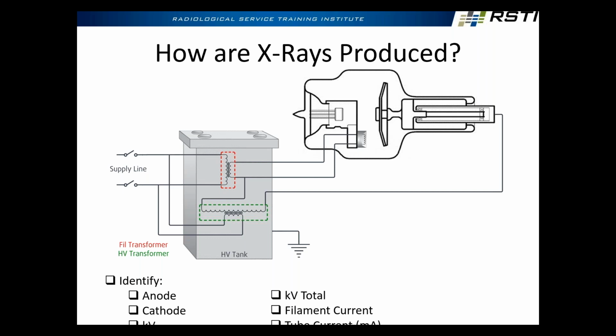On the left-hand side, we have the cathode. On the right-hand side, we have the anode or target. The cathode usually contains a pair of filaments, a small filament and a large filament, that provide us with a small and large focal spot. Those do a couple of things for us. Generally speaking, resolution is controlled by focal spot size. The smaller the focal spot, the sharper the image. However, the smaller the focal spot, the shorter my exposures can be. So if I need to do a longish exposure on a larger mammal, then I might need to switch to the large focal spot in order to get that kind of output.